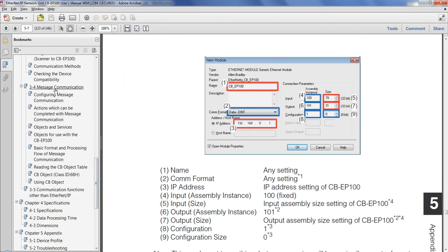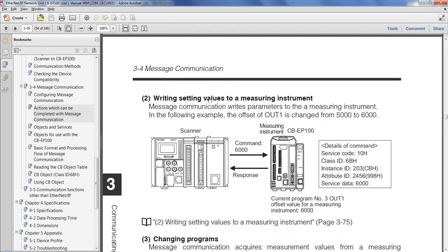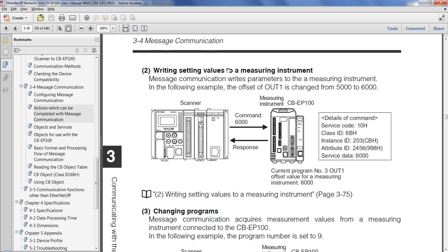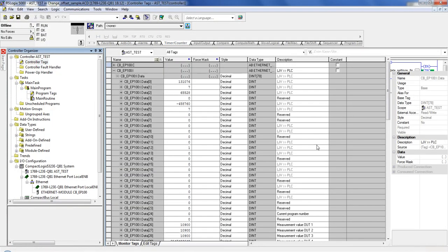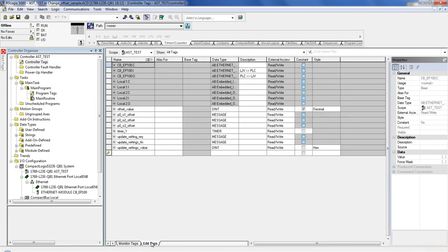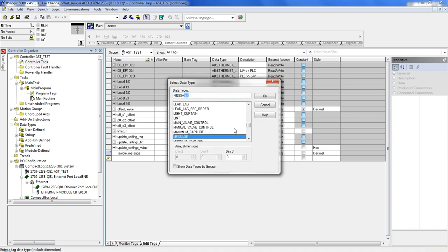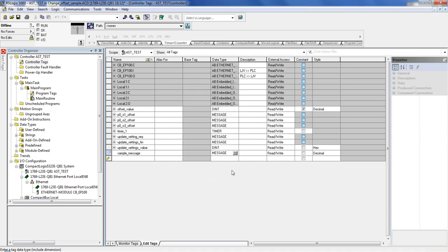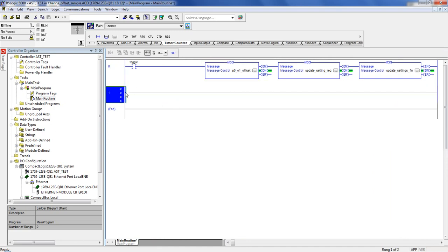We go to 3-4, message communication, and then let's go ahead and look at the actions which can be completed with message communication. So what we want to do is write settings to a measuring instrument, essentially writing values to the LJV. This particular one is saying, let's change the offset of out 1. So what we do is, because it's a message command, we go to, let's just say controller tags for now, edit tags, and I want to create a new tag. I've already made a couple of them here, but I'm going to run through how to make it real quick, just to demonstrate. So sample message, and then over here, before pressing enter, let's go ahead and choose message. So that's now a new message that I've created.